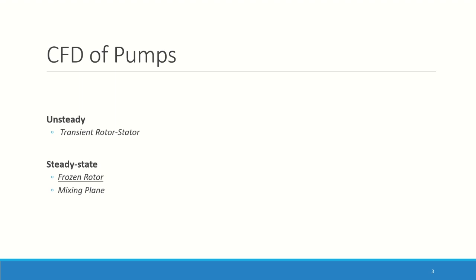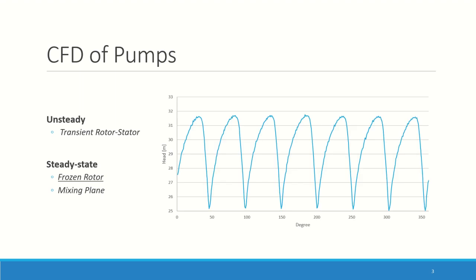The disadvantage of the frozen rotor is that it's basically a snapshot of the unsteady simulation. But as you can see, the head, torque, efficiency, and all variables inside the pump can vary a lot. They are very unsteady, mainly due to the big interaction between the rotor and the stator. The tongue of the volute or the cut water is going to introduce all these peaks when the blade is passing close to it. This is why the frozen rotor approach is not the best. If you want an average value of the head, it's better to compute many positions and take average. The mixing plane approach gets rid of all interaction and makes a circumferential averaging at the interface, giving closer value to unsteady simulation.